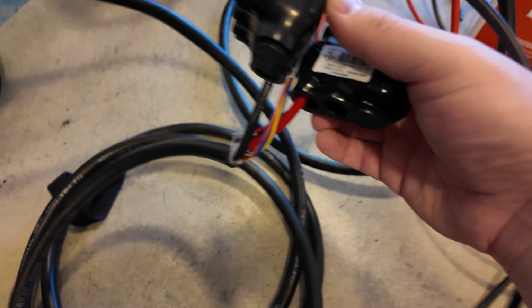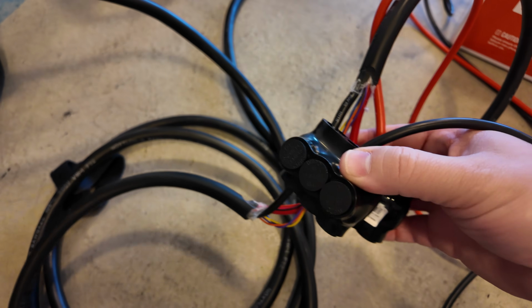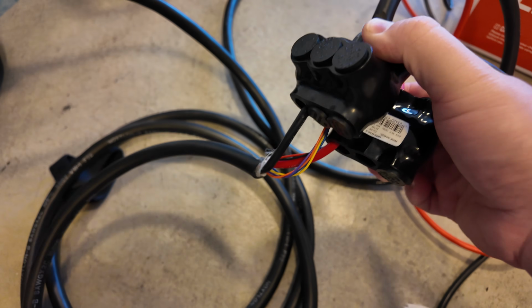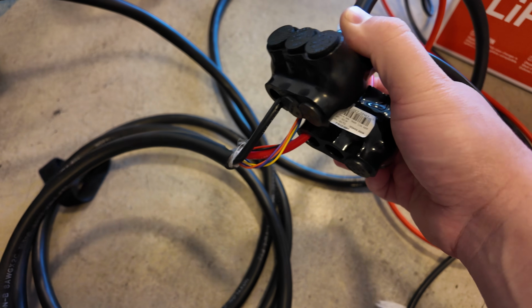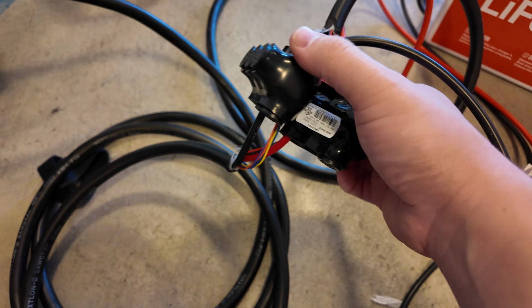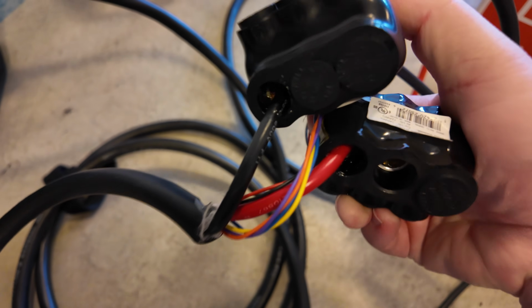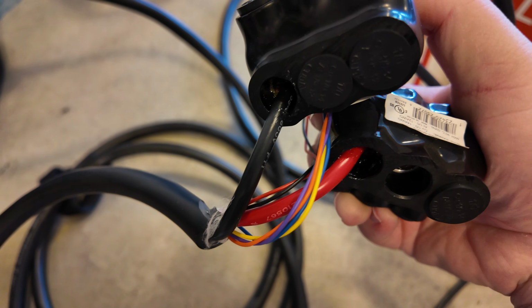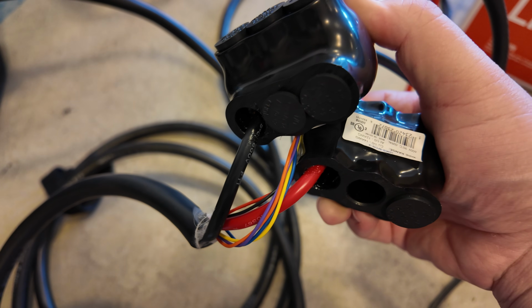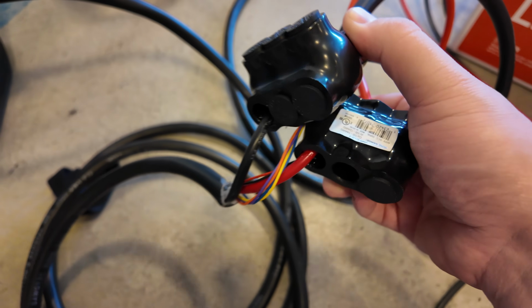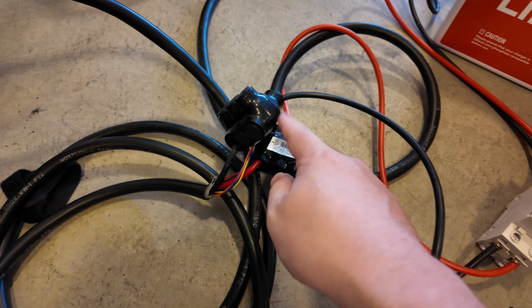One more thing: these splice connectors, I call them Polaris connectors. They're similar to that, but not that particular brand. These are UL listed, however. These particular ones can accept very large wire, I think all the way up to like 1/0 size down to 14 gauge. So it works great for this 8 gauge wire.